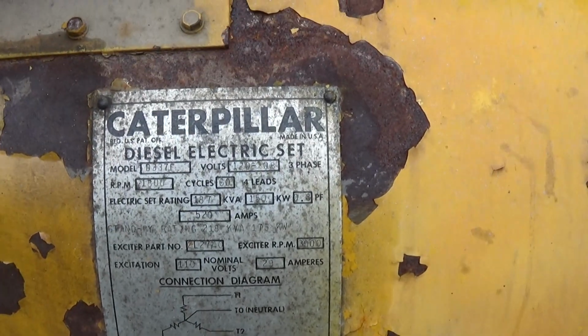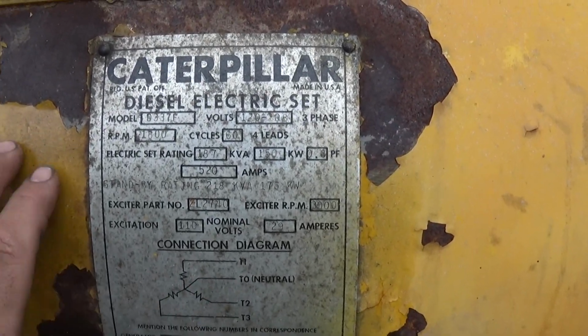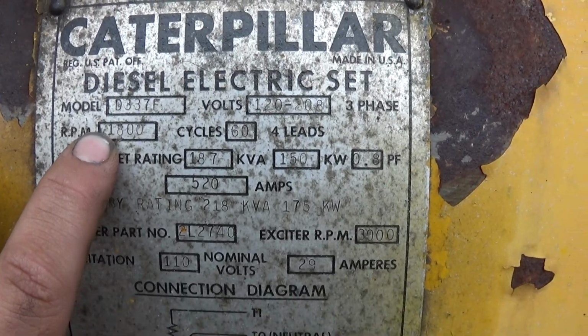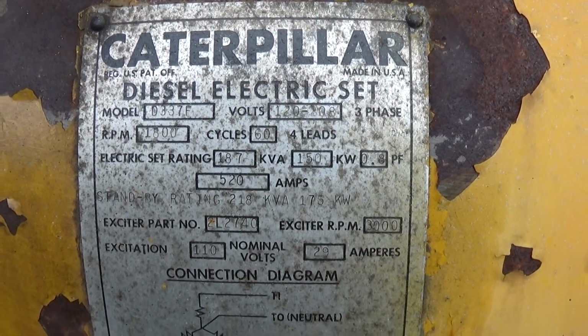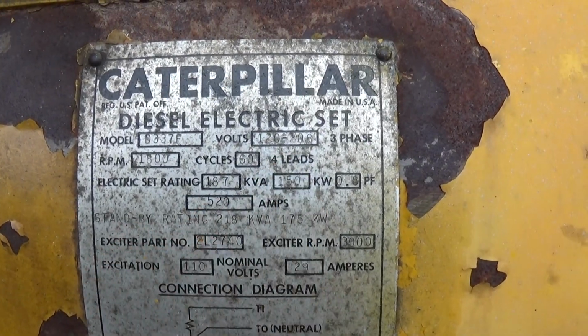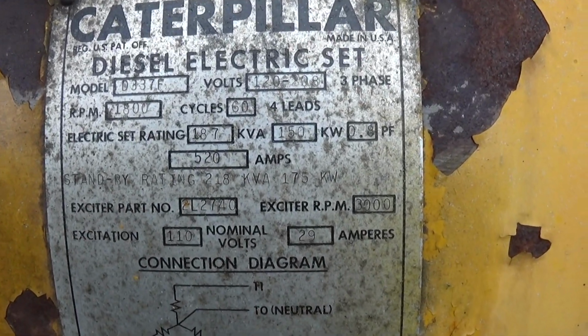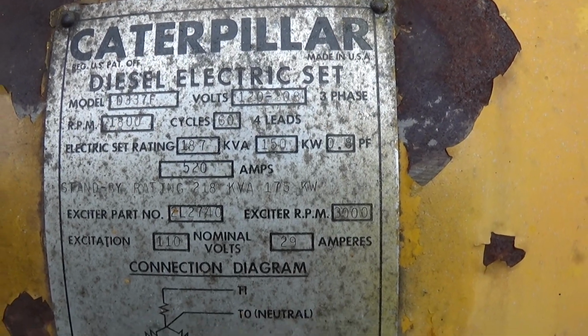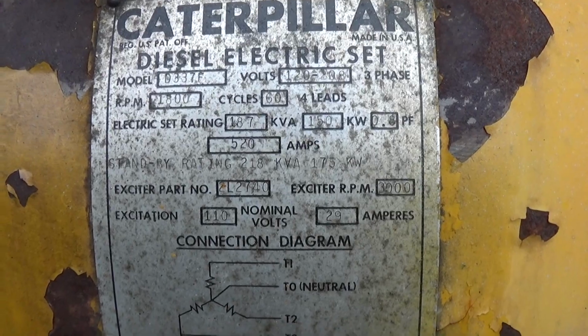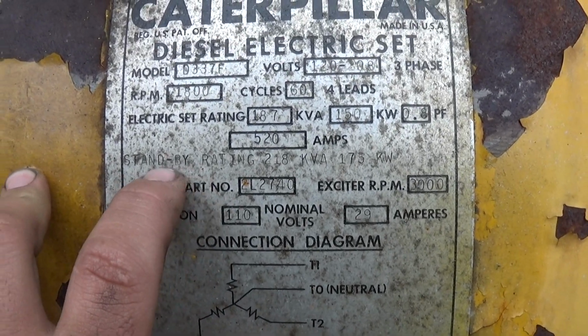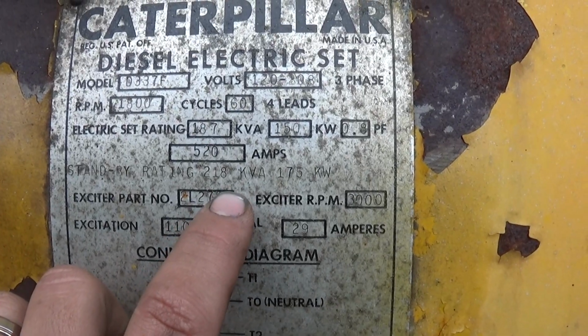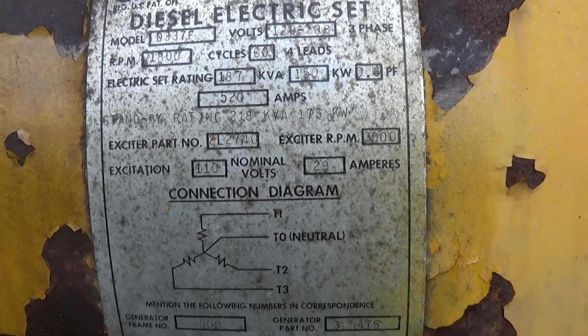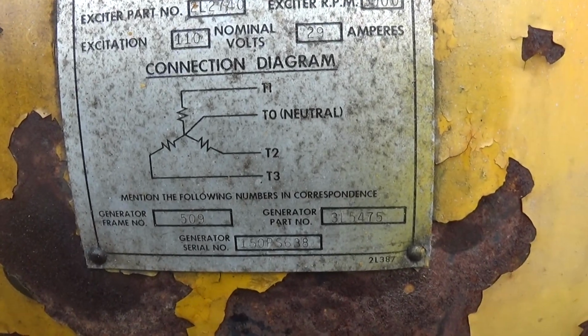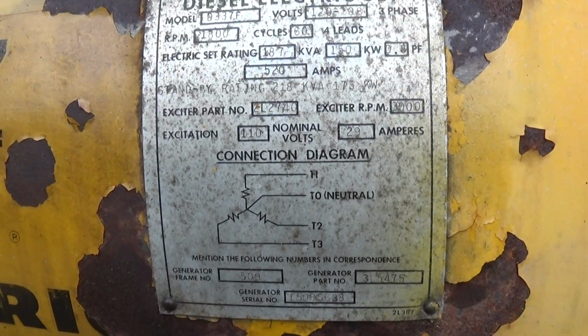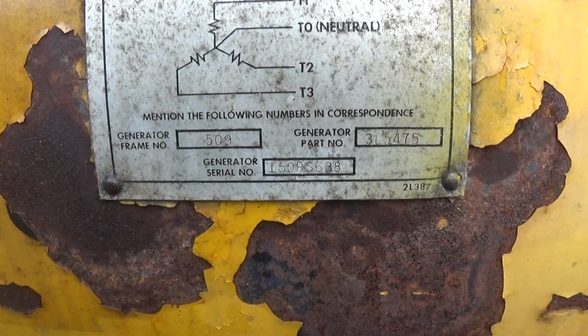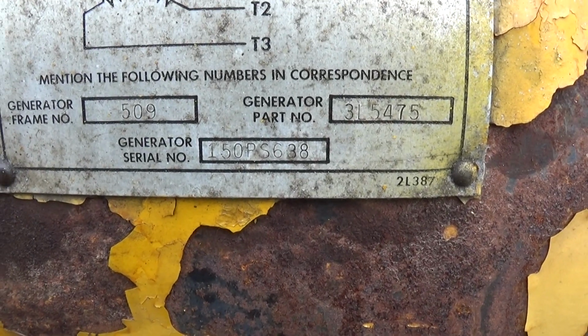So this is the electric set nameplate for the total unit. It's a D337F, a 120/208 3-phase genset. It is not reconnectable, it's only 4-wire, 4-lead, 1800 RPM, rated at 150 kilowatt. Now that's its continuous rating. Somebody has stamped, I'm guessing the factory did this, its standby rating, which is typically a 4-hour rating, at 175 kilowatt. Then we've got some exciter information and a wiring diagram, not much to it since it's not a reconnectable genset, and there's the gen serial number.